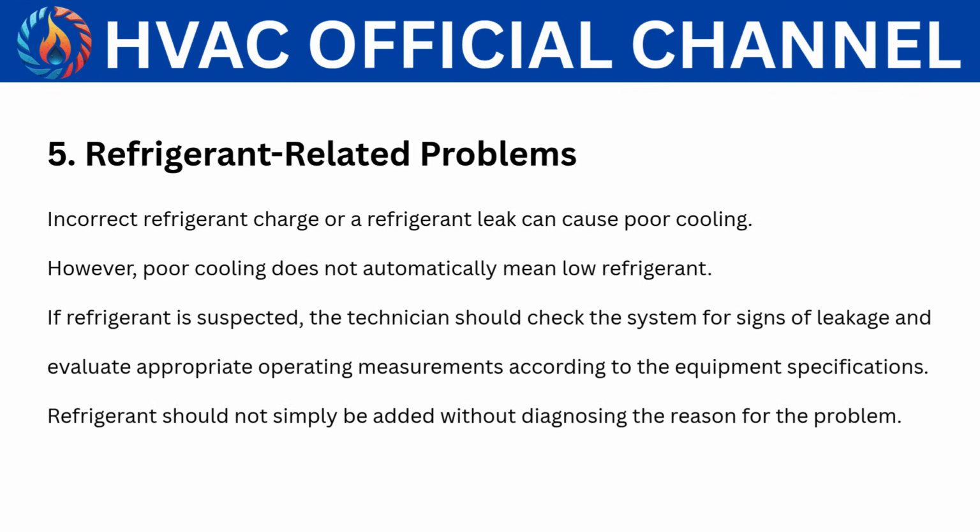5. Refrigerant-related problems. Incorrect refrigerant charge or a refrigerant leak can cause poor cooling. However, poor cooling does not automatically mean low refrigerant. If refrigerant is suspected, the technician should check the system for signs of leakage and evaluate appropriate operating measurements according to the equipment specifications. Refrigerant should not simply be added without diagnosing the reason for the problem.